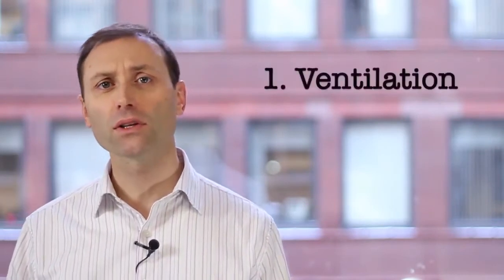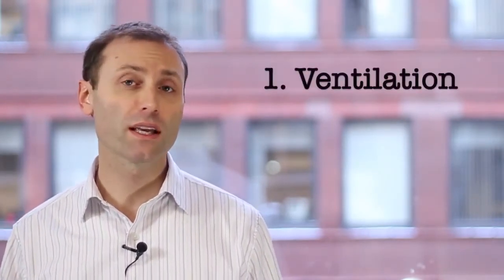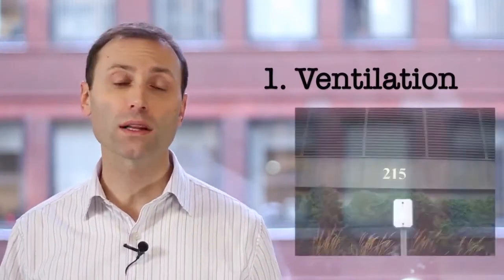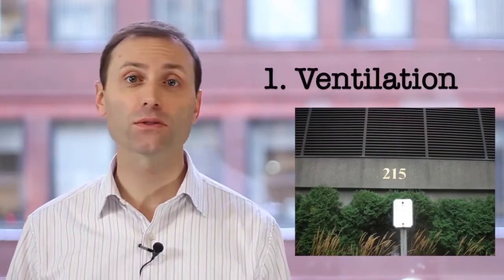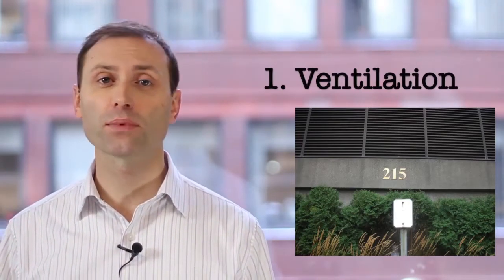Number one, check on a building's ventilation. It's important to see if the building is bringing in the proper quality and quantity of outdoor air. Check those outdoor air intakes and look for any nearby pollution sources.